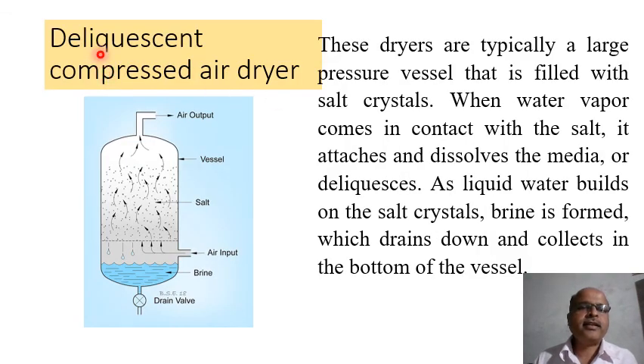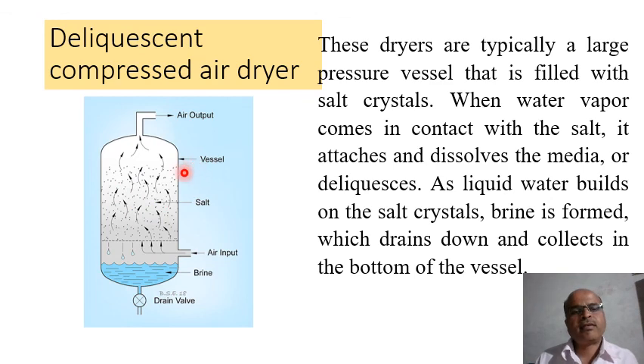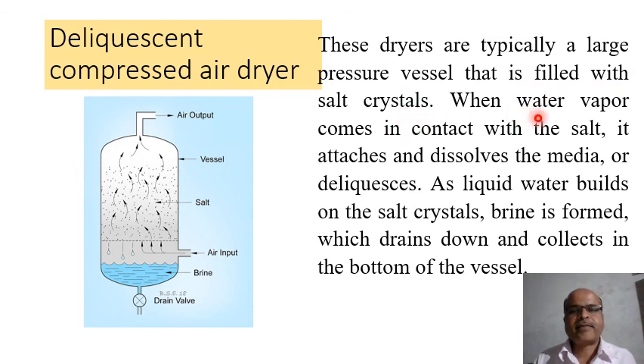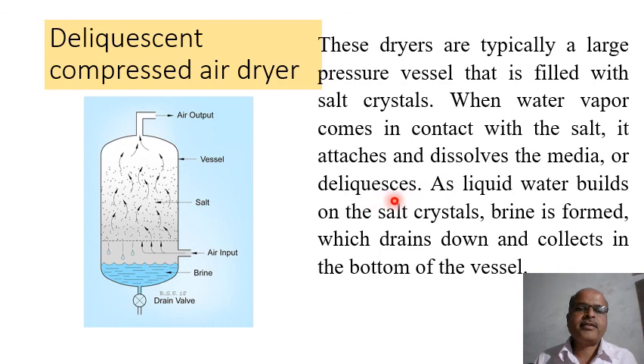Deliquescent compressed air dryer: The diagram shows air input, a vessel filled with salt crystals, and a drain valve. These dryers are typically a large pressure vessel filled with salt crystals. When water vapor comes in contact with the salt, it attaches and dissolves the media — or deliquesces. As liquid water builds on the salt crystals, brine is formed which drains down and collects in the bottom of the vessel.